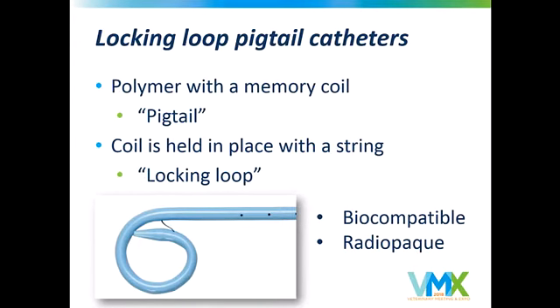So the locking loop pigtail catheter is a relatively new invention in medical science and has been really transformative as far as our options for managing various conditions. It all starts basically with a plasticky polymer that has a memory coil. This little piece of plastic is designed and determined to be this shape. If you force it to go straight, it will temporarily be straight. But as soon as you let the plastic go, the polymer's memory is going to make it go back into this little pigtail. So any catheter that has a memory, we call it a pigtail catheter.